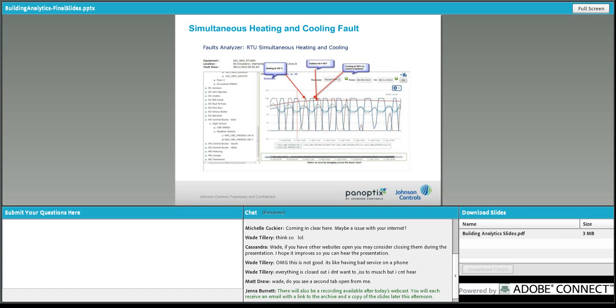Let's go into a couple of specific examples. I'll talk about two very different kinds of FDD, the first being rules-based FDD. Here's an example from the Panoptix Continuous Diagnostic Advisor of a rule showing a simultaneous heating and cooling fault. As you can see on the screen, there are several graphs of data. If you look in the middle, you can see a red line—that's where the fault was shown for this example.